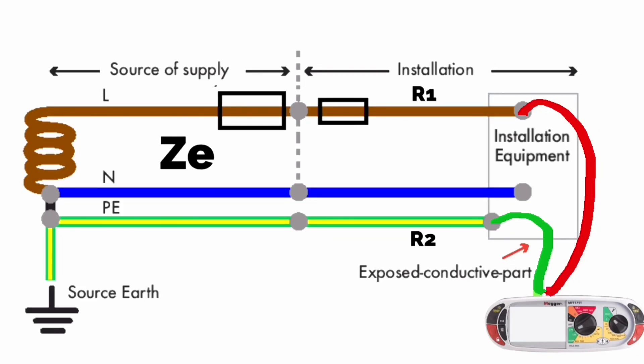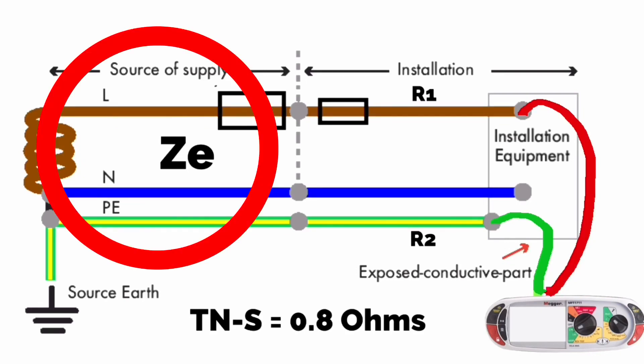The maximum impedance of the supply authority's cable depends on the earthing arrangement. The drawing shown here is a TNS earthing arrangement. The supply authority's maximum impedance of that cable ZE is 0.8 of an ohm.